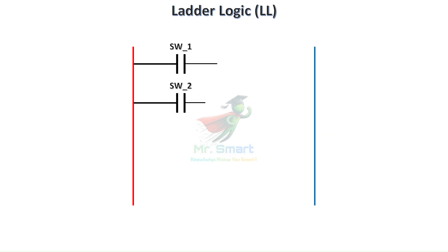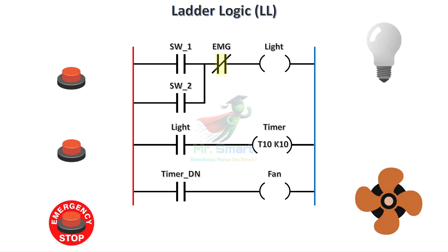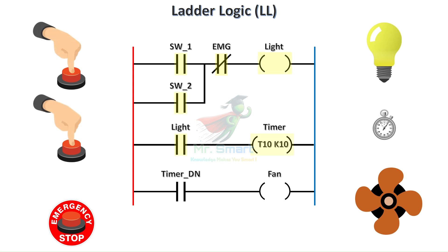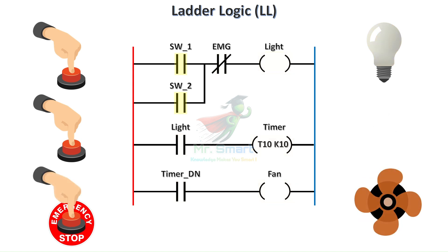Ladder diagram, or ladder logic, is the most popular PLC programming language and has its roots in electrical engineering. It visually resembles a ladder with rungs that represent logical operations. Each rung describes a control process, like turning on a motor when a switch is pressed. It's intuitive for electricians and technicians because it mimics the layout of physical relay circuits. Ladder logic is excellent for discrete control systems such as start-stop operations, alarms, and interlocks.